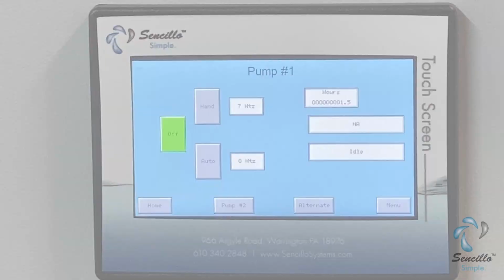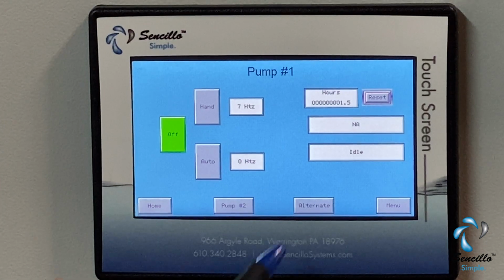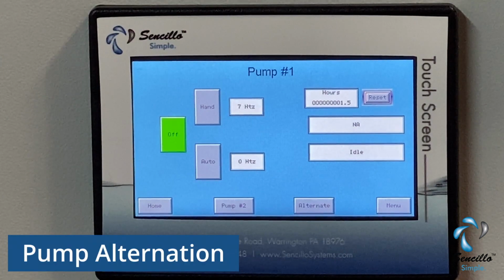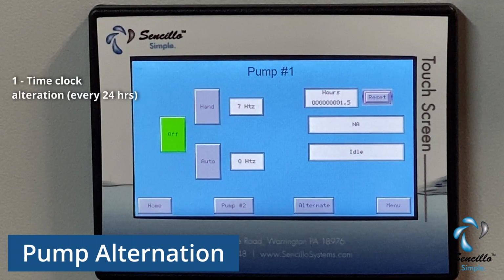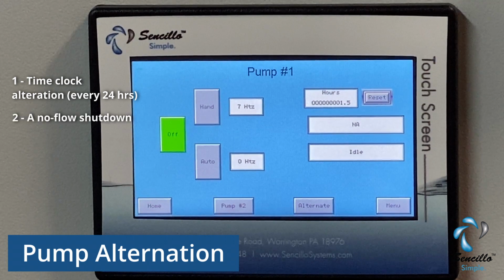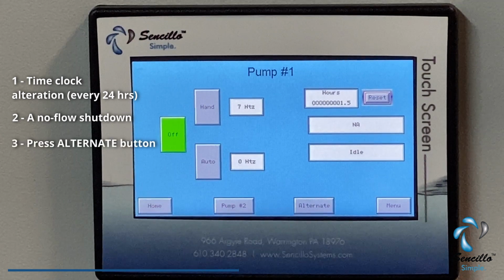Now we're going to talk about pump alternation. The pump will alternate under 3 conditions. 1, based off a time clock, which is factory programmed at 24 hours. 2, if there is a no flow condition, once the pump's shut down, they will alternate. And 3 will be by pressing the alternate button on the screen.